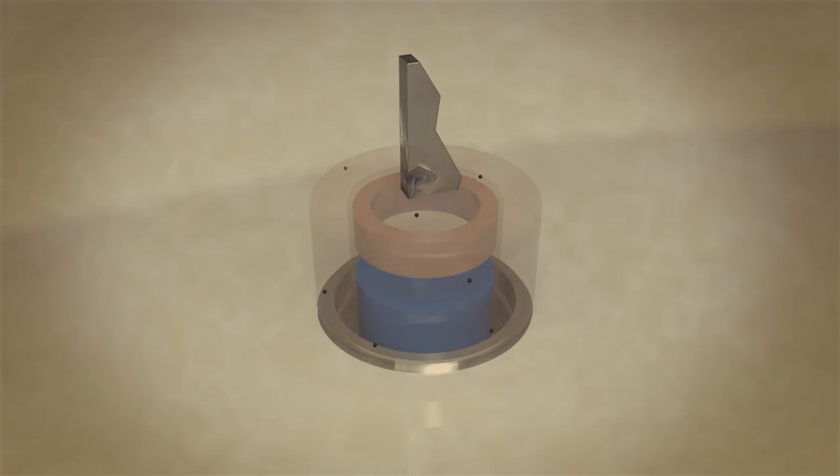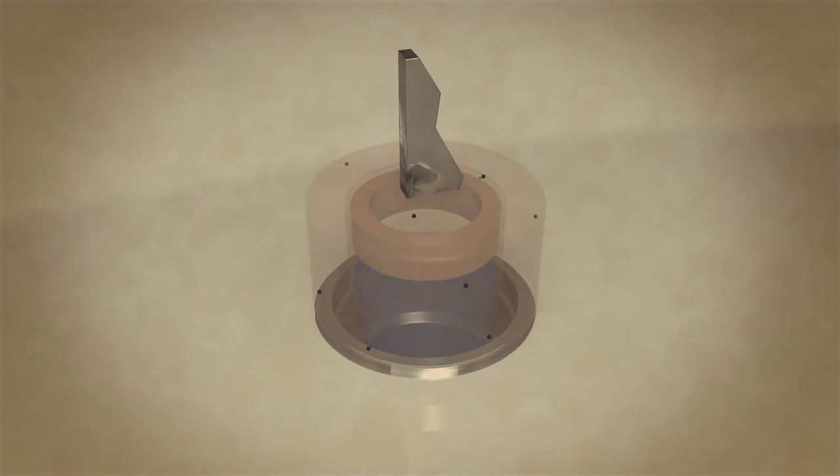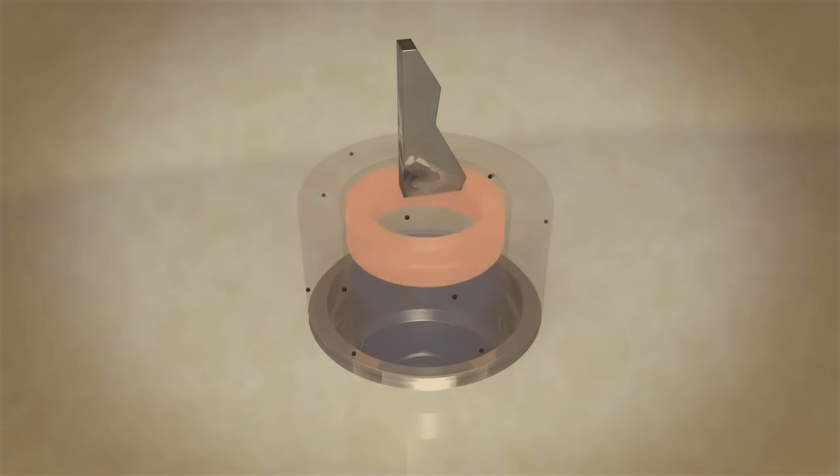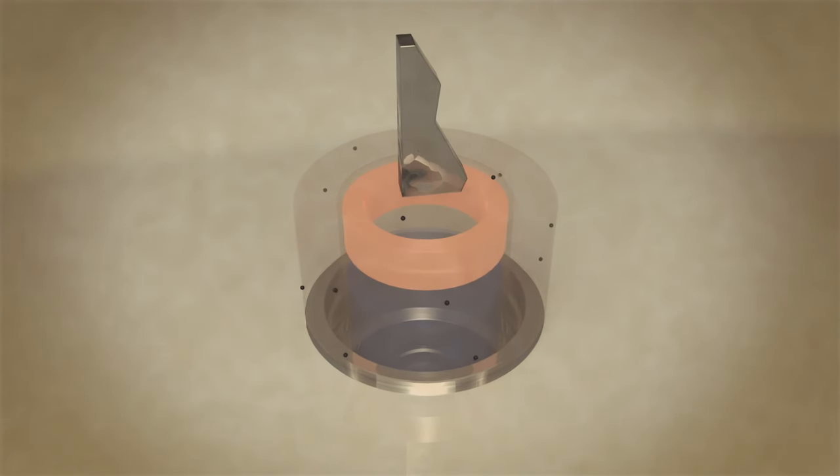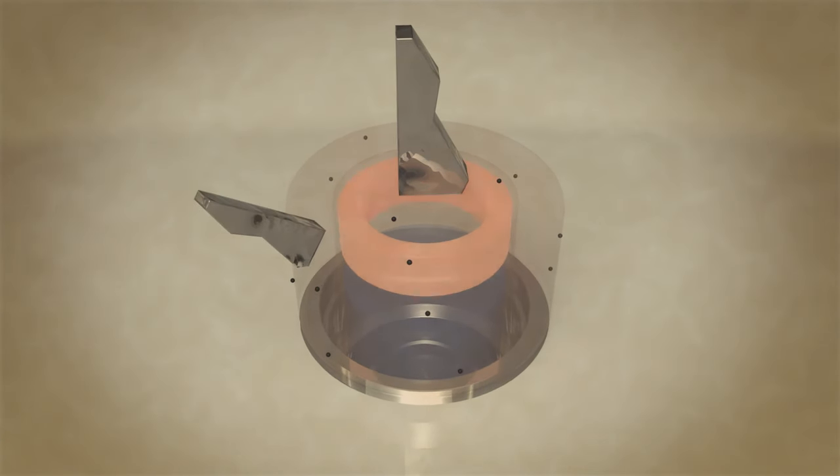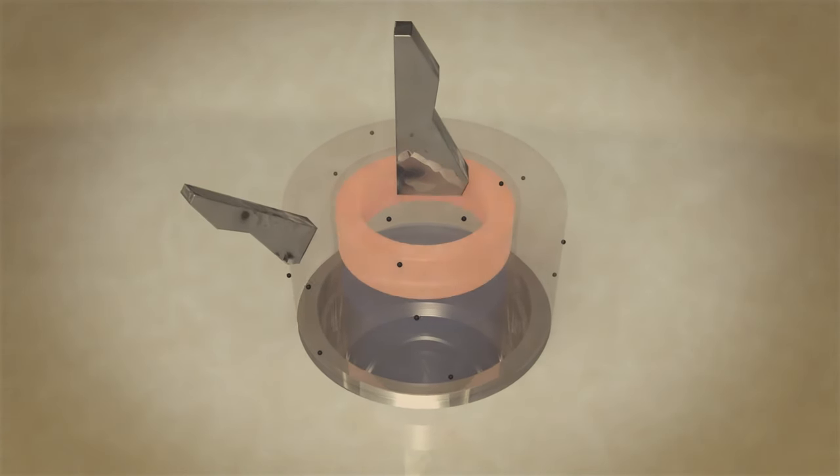Inside the tip of the sensor is an inductive coil, used to determine the concentration and particle size of debris on the sensor tip.